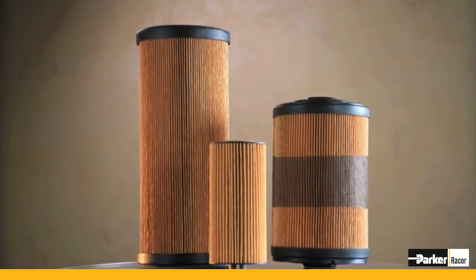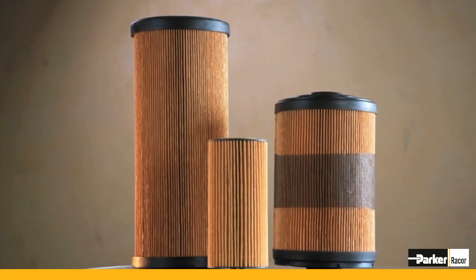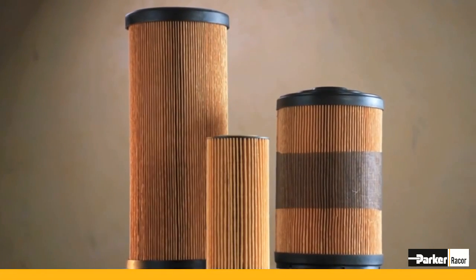That's fine, it's a cleaner fuel, but in order to get your fuel that clean, diesel fuel was subjected to hydrotreating. In addition to removing the sulfur, however, hydrotreatment also removed the native chemicals within the diesel fuel that gave it a natural lubricity. In response to that, the additives business responded with tried and true lubricity additives that improved the lubricating capability of the fuel. The lubricity additives, which belong to a chemical class known as surfactants, caused water to exist in much smaller droplets and stabilized those droplets in the fuel. So every fuel filtration media that is designed to remove water from diesel fuel was disarmed by this new fuel.